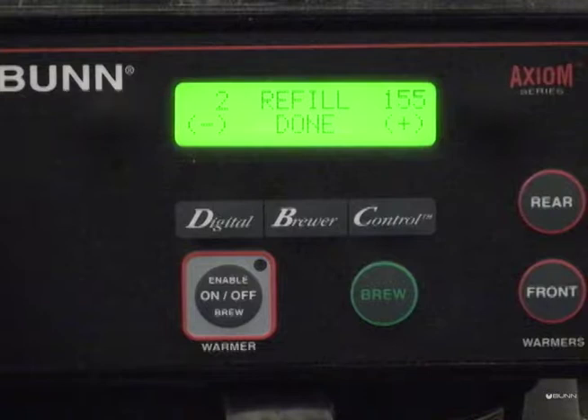This number is a factory set threshold number of 155. The number is adjustable according to water conductivity. The threshold number is the trigger point for activating the refill circuit. This is why it is important to check or adjust for naturally soft water and the use of reverse osmosis filter systems.